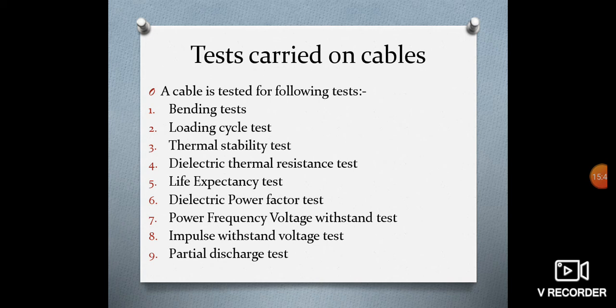HVDC of 1.88 times the rated DC voltage of negative polarity for 30 minutes is applied, and the cable is said to have withstood the test if no insulation failure takes place.